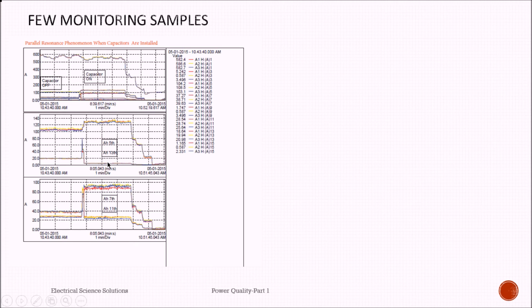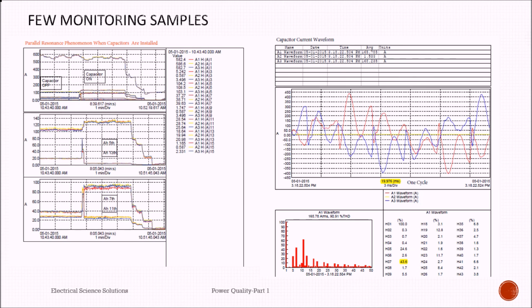Now when this kind of parallel resonance happens, you see very high harmonic currents flowing through the capacitor, and this will damage your capacitors very soon. So premature failure of capacitors can happen, but this can be prevented if you monitor it at a very early stage.